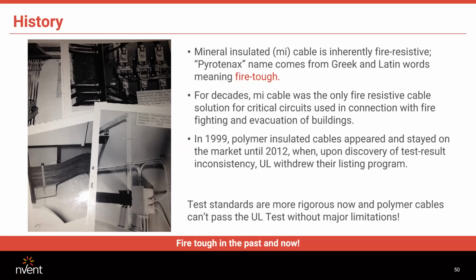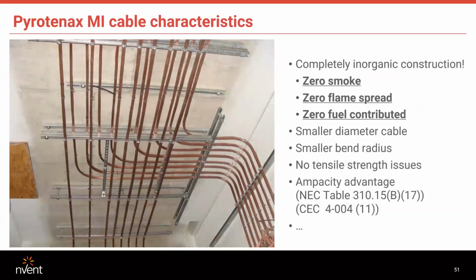I mean, you want it to be 100%. This is life safety. A .300 batting average may be good in Major League Baseball, but it won't cut it for life safety systems. So the polymer cables were delisted, and then new testing was put in place. And I'm going to expound on that a little bit more later in the presentation.